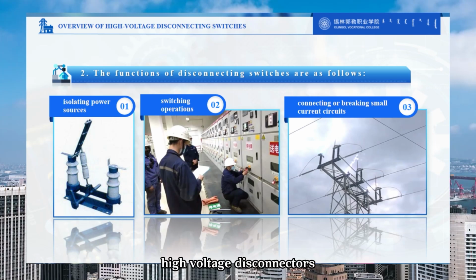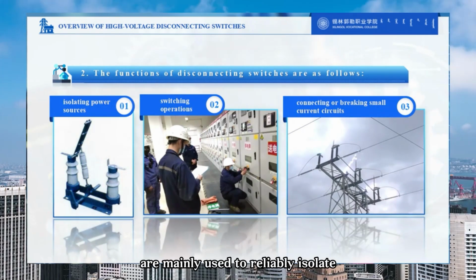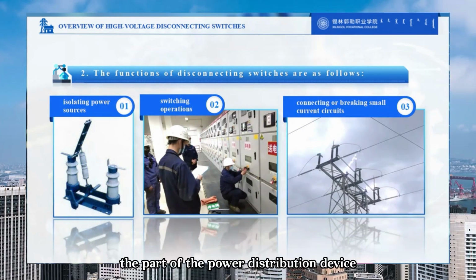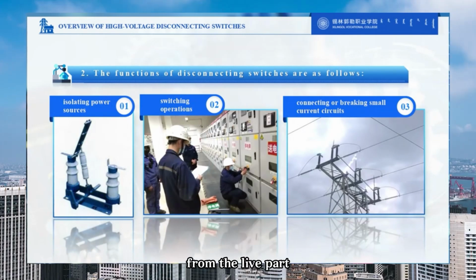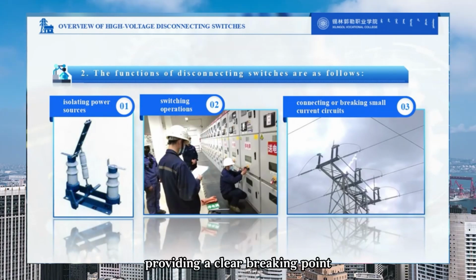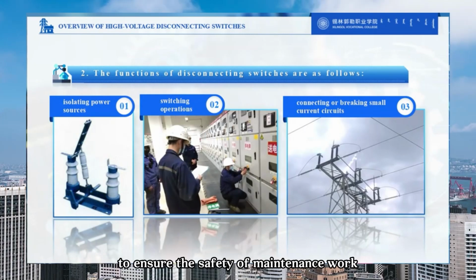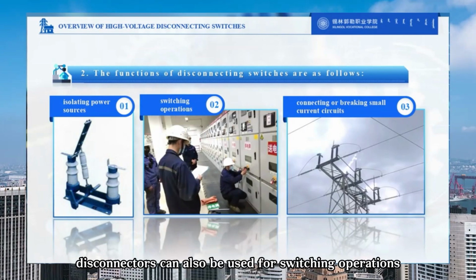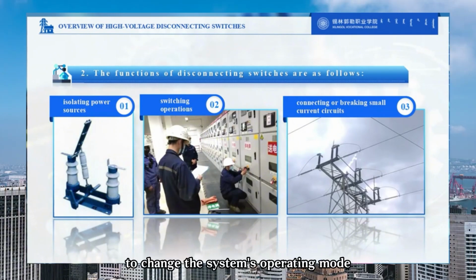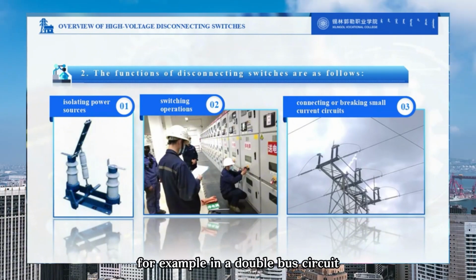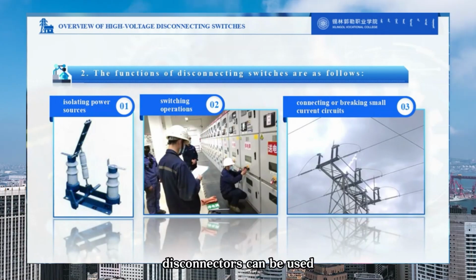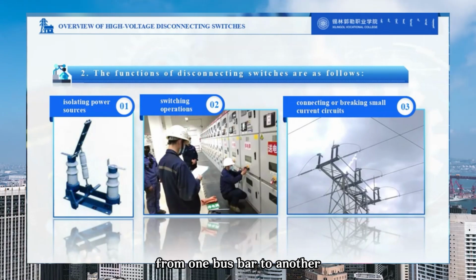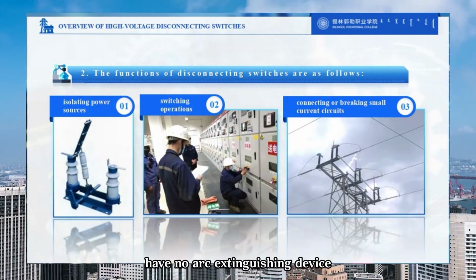High-voltage disconnectors are mainly used to reliably isolate the part of the power distribution device that needs to be de-energized from the live part, providing a clear breaking point to ensure the safety of maintenance work. Disconnectors can also be used for switching operations to change the system's operating mode. For example, in a double bus circuit, disconnectors can be used to switch the operating circuit from one bus bar to another.